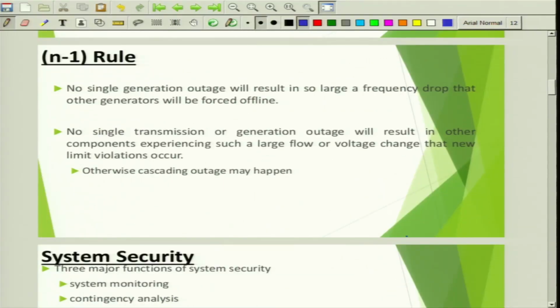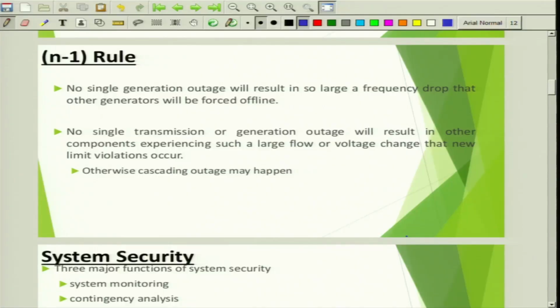So the n-1 rule is very important. No single generation outage will result in so large a frequency drop that other generators will be forced offline. Any generator you pick, you assume that it is taken out of the system for the time being, and check whether you are still able to maintain system stability in terms of voltage stability, frequency stability and other things. No single transmission or generation outage will result in other components experiencing such a large flow or voltage change that a new limit violation occurs, right. We should not allow a new limit violation to take place. Otherwise, a cascading outage may take place.